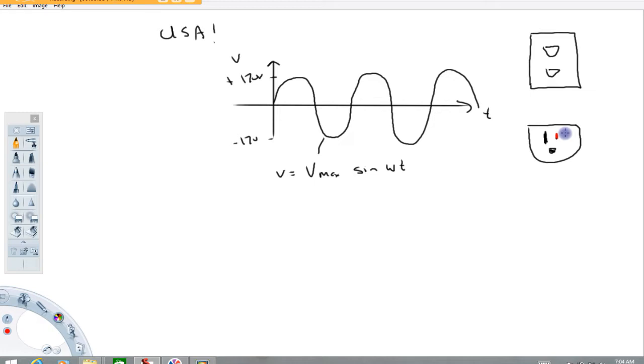This guy right here is the neutral line. This completes the circuit. This one right here is just a ground. And what I love about the term ground is you can't mean it more literally. If you follow the wires all the way through the building, through the circuit breaker, this is eventually connected to usually an 8 or maybe 12-foot copper rod, or sometimes aluminum rod, that's driven into the earth. So this one's for safety. This one's driving the circuit. This one's completing the circuit.